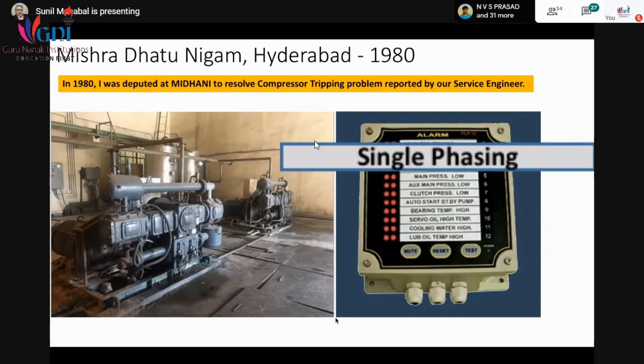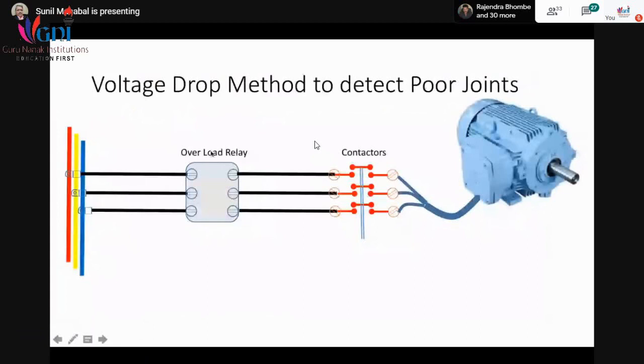There is one overload relay connected to the bus bar. This is RYB. There is a lug and then the cable, which goes through the overload relay and reaches the contactor. If it is a star delta motor, then there will be three contactors. If it is a slip ring motor, then there will be only one contactor. But you just understand the concept. This cable finally reaches the motor.